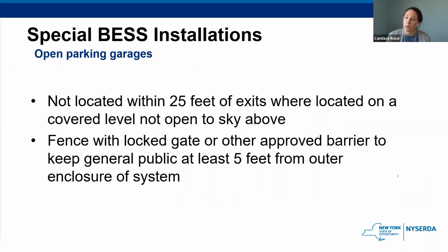So here are the open parking garage additional requirements. In addition to avoiding air inlets, open parking garage installations should not be located within 25 feet of exits on covered levels and should be secured with a fence or other barrier to keep people at least 5 feet from the outer enclosure of the system.